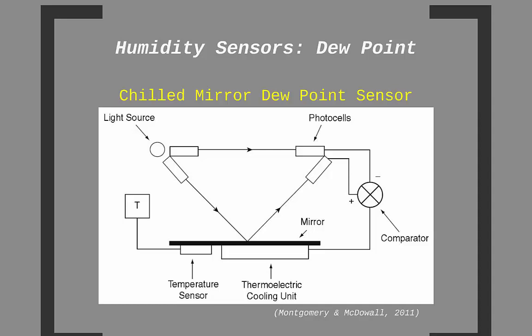There are several styles out there, to include lithium chloride dew point sensors and psychrometers, but we will only provide a how-it-works tutorial for a device called the chilled mirror dew point temperature sensor. Basically, you have a contraption like the one shown here, placed in a location where the humidity level is to be measured. There is a light source, which directly shines some light onto the upper photocell. The same light source also reflects light off a mirror and onto the lower photocell.